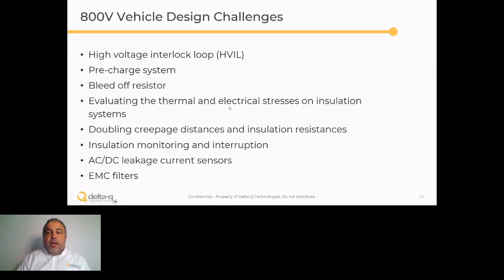Some systems employ pre-charge systems to prevent a large inrush of current from moving through the power system when it's turned on, which could otherwise cause a lot of damage and dangerous situations for those working with the system. There may also be a need for bleed-off resistors that help to safely bleed off energy after it is disconnected. Due to the high levels of capacitance in high voltage systems, there can be a lot of voltage and power still remaining after disconnection.